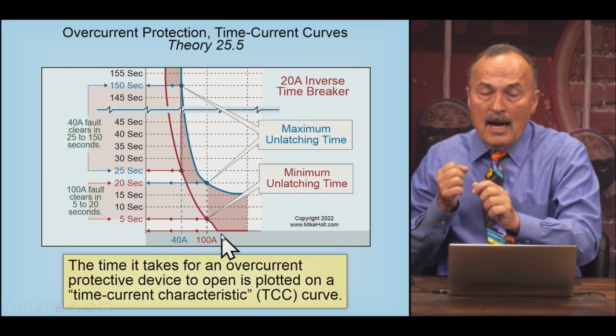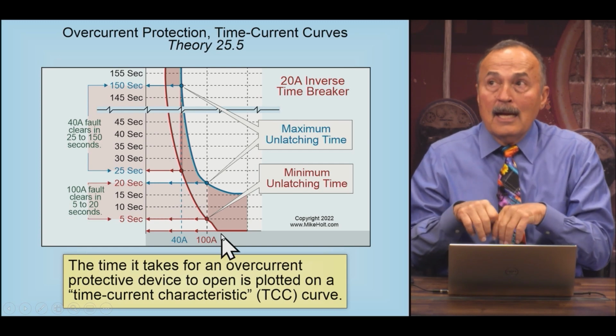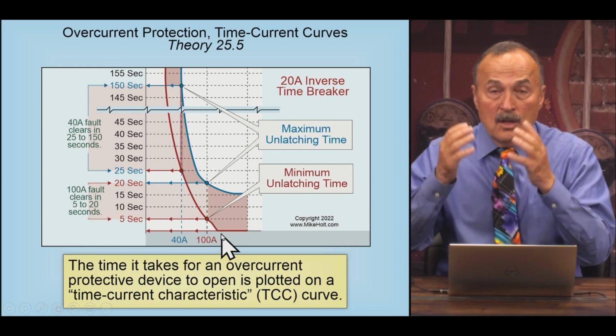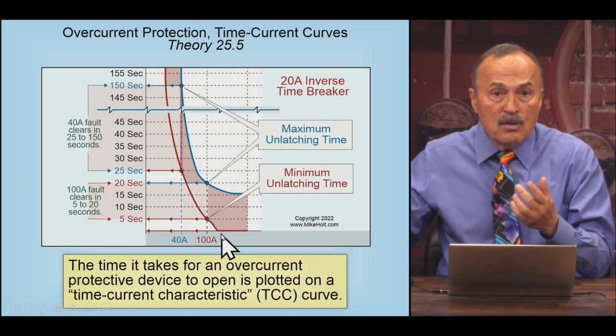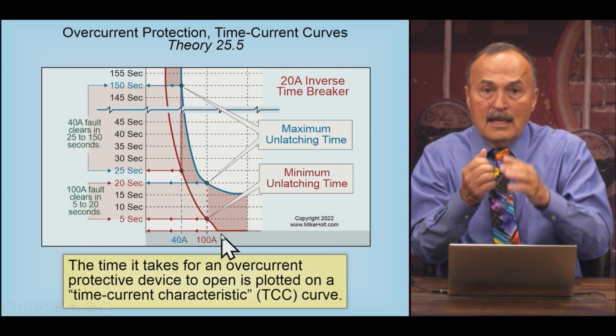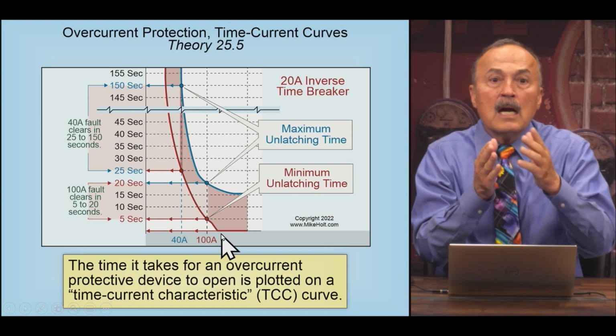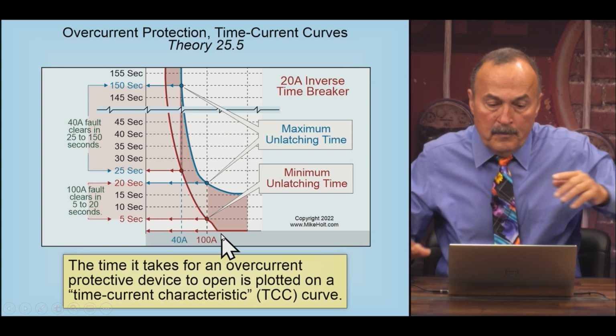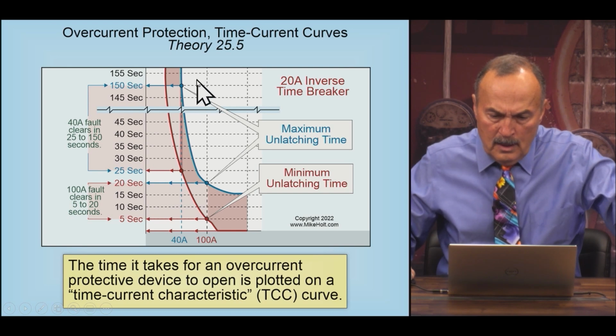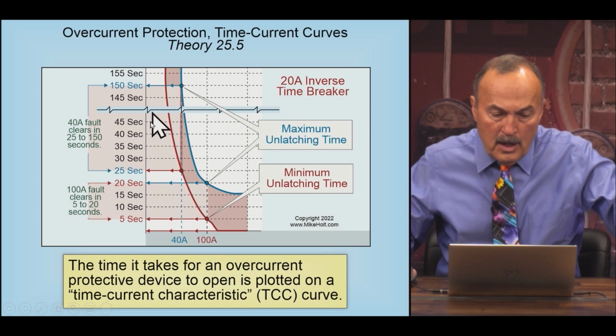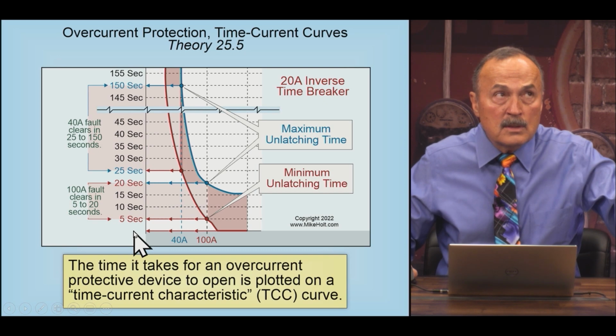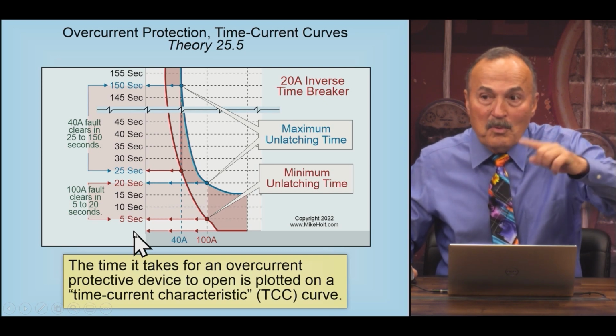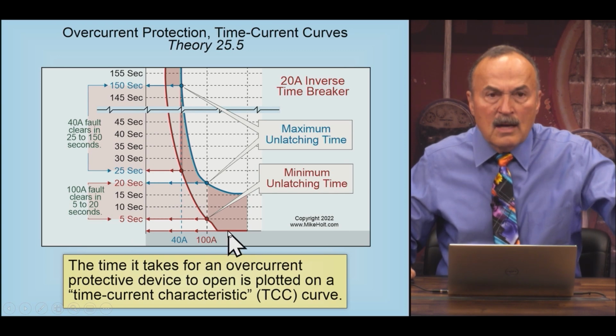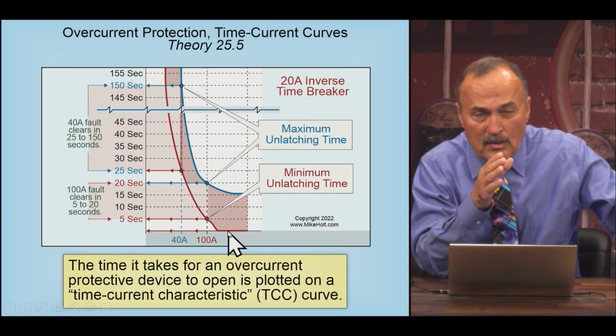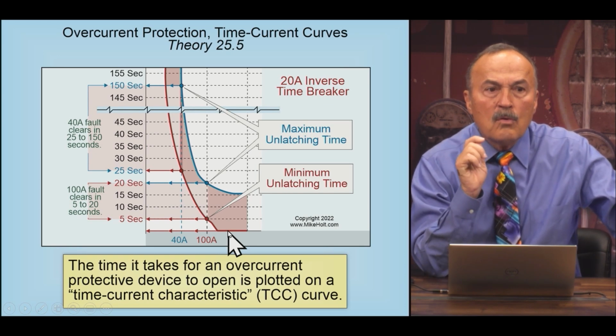Now that field is doing what? It's unlatching. And Brian, you said, well, circuit breakers take time because it's a mechanical device. So we have this high electromagnetic field. That high electromagnetic field is now going to unlatch it, and then it takes some physical time for it to actually open up the contacts. So watch what we're talking about here. If you have an overload condition, it's going to take time. In order to get down to the 0.01 time, which is 10/100ths of a second, remember the decimals, the number of decimal places we talked about in math? You're going to have to get to some value that's going to go to, correct me if I'm wrong, Tom, the instantaneous trip range.